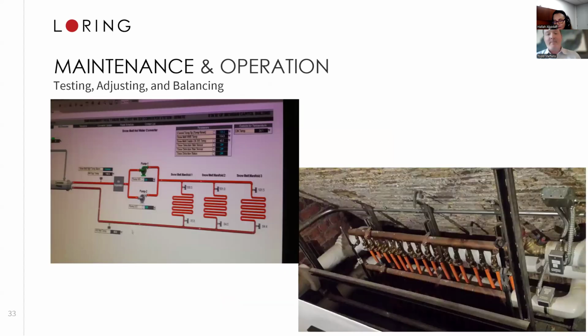Next one. Just another example of where the BAS and the actual balance of the system can be a little bit deceiving is yet another shot from the Michigan State Capitol building. This is a hot water system dedicated to an under-slab snow melt system on the walkways leading up to and around the Capitol. The shot on the left is a screenshot of their BAS, showing pumps active to circulate the hot water through the circuits.